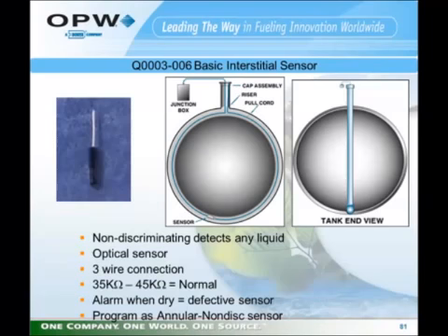The Q0003-006 basic interstitial sensor is a non-discriminating optical liquid sensor. It's used in the same spaces the -003 sensor is used. It just does not have the hydrocarbon sensing metal tabs on the sensor. It is a 3-wire connection, but it is, like I said, non-discriminating. If it alarms when it's dry, it's defective, and it's programmed as an annular, non-discriminating sensor.